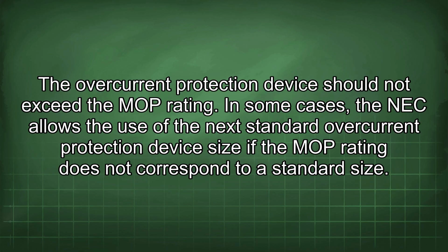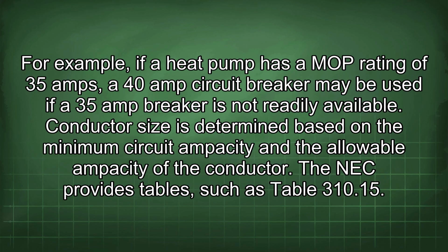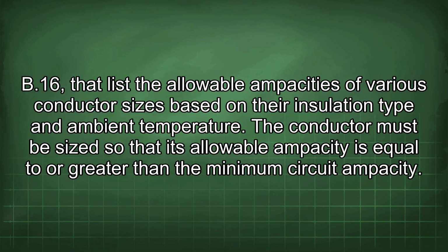In some cases, the NEC allows the use of the next standard overcurrent protection device size if the MOP rating does not correspond to a standard size. For example, if a heat pump has a MOP rating of 35 amps, a 40 amp circuit breaker may be used if a 35 amp breaker is not readily available. Conductor size is determined based on the minimum circuit ampacity and the allowable ampacity of the conductor. The NEC provides tables, such as Table 310.15(B)(16), that list the allowable ampacities of various conductor sizes based on their insulation type and ambient temperature.